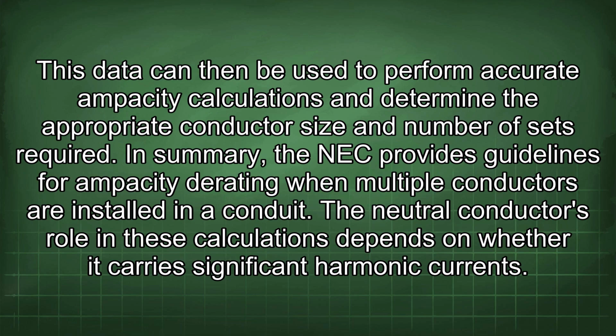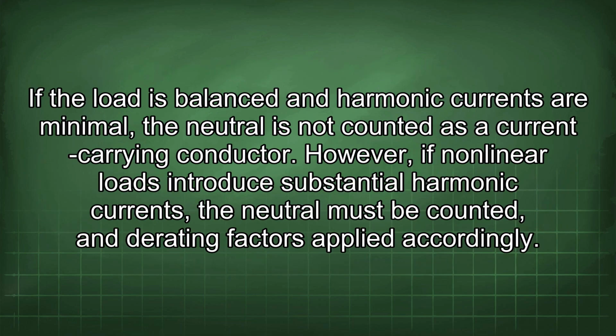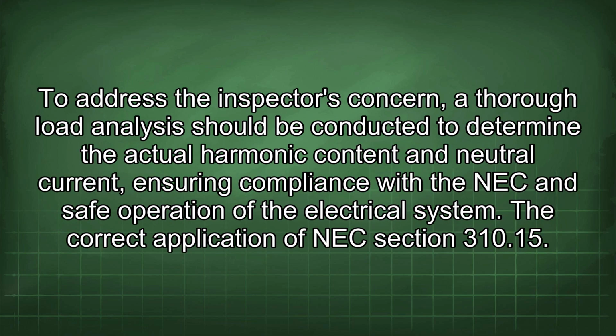The neutral conductor's role in these calculations depends on whether it carries significant harmonic currents. If the load is balanced and harmonic currents are minimal, the neutral is not counted as a current-carrying conductor. However, if nonlinear loads introduce substantial harmonic currents, the neutral must be counted, and derating factors applied accordingly. To address the inspector's concern, a thorough load analysis should be conducted to determine the actual harmonic content and neutral current, ensuring compliance with the NEC and safe operation of the electrical system.